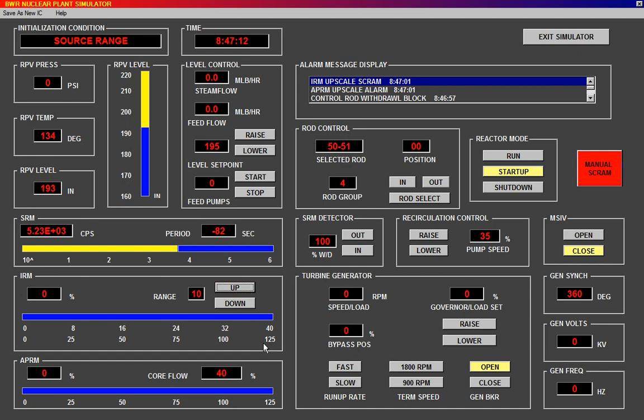so I screwed everything up because I reached 120 in this scale because I was not being careful taking out rods. And the period got too low, so I could not control it anymore, and this just stopped all the reactor, and now we need to start from scratch again with the source range monitor, etc. So when you are in this intermediate range, don't get confident because of this heating water. Just keep taking out rods slowly. You can be a bit faster, but don't be too confident, and always be careful not to reach this 120 value here.